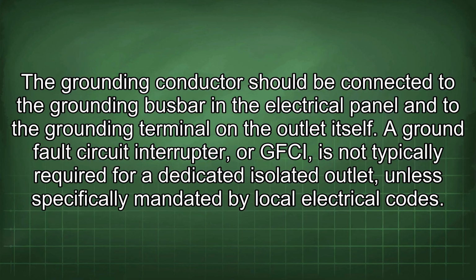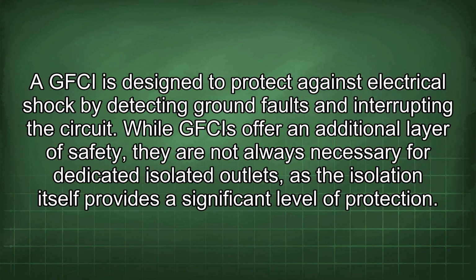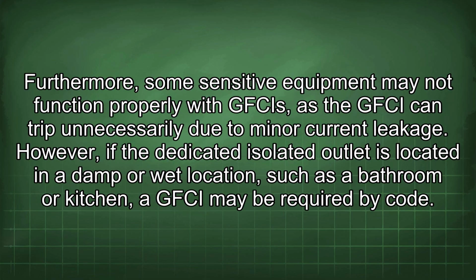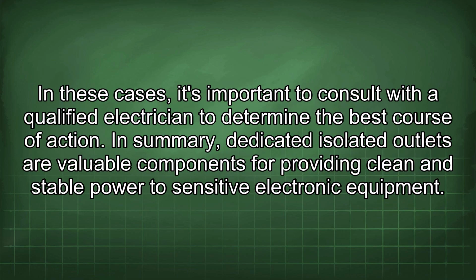A ground fault circuit interrupter, or GFCI, is not typically required for a dedicated isolated outlet unless specifically mandated by local electrical codes. A GFCI is designed to protect against electrical shock by detecting ground faults and interrupting the circuit. While GFCIs offer an additional layer of safety, they are not always necessary for dedicated isolated outlets, as the isolation itself provides a significant level of protection. Furthermore, some sensitive equipment may not function properly with GFCIs, as the GFCI can trip unnecessarily due to minor current leakage. However, if the dedicated isolated outlet is located in a damp or wet location, such as a bathroom or kitchen, a GFCI may be required by code. In these cases, it's important to consult with a qualified electrician to determine the best course of action.